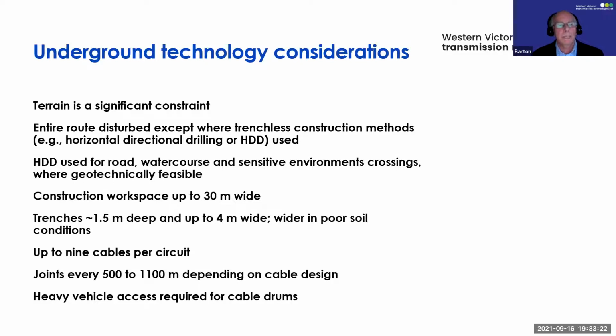Some considerations for underground technology: terrain is a significant constraint. Overhead technology can span difficult terrain because towers are approximately 450 to 500 metres apart. With underground cables, the entire route needs to be disturbed unless we use trenchless construction methods or horizontal directional drilling, where geotechnically feasible. Slope becomes very important, as we cannot run across side slopes like transmission lines can, since we'd need to cut a substantial road to accommodate the trenches. So we prefer to run up slopes, perpendicular, along ridges, which constrains the route and adds length compared to an overhead route.